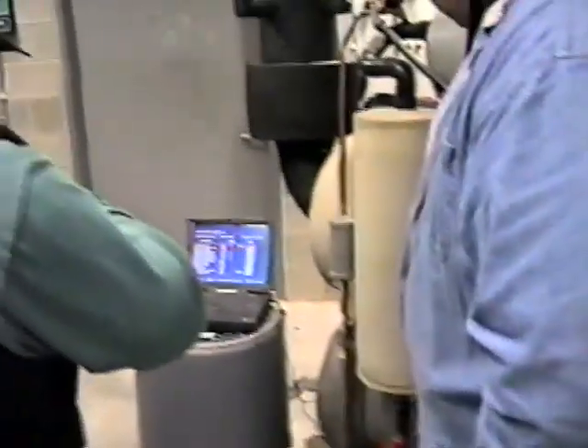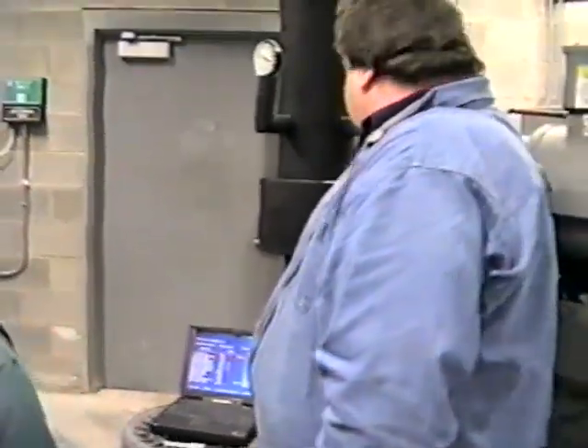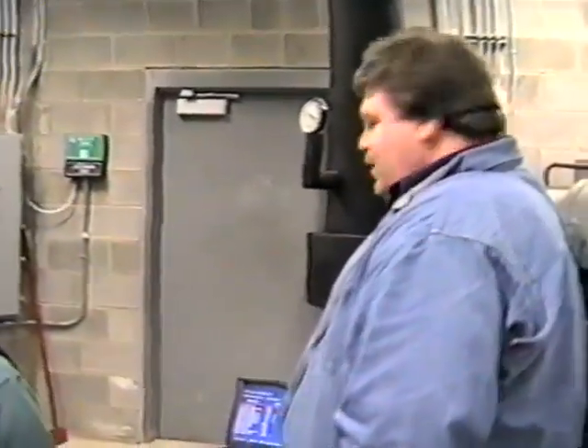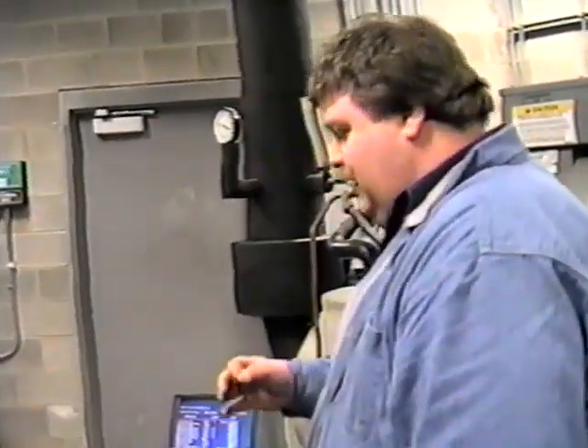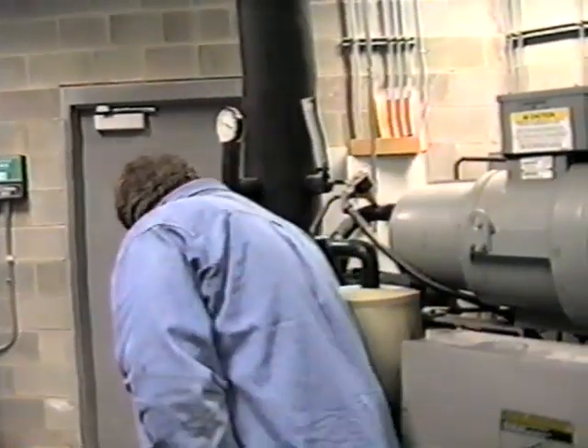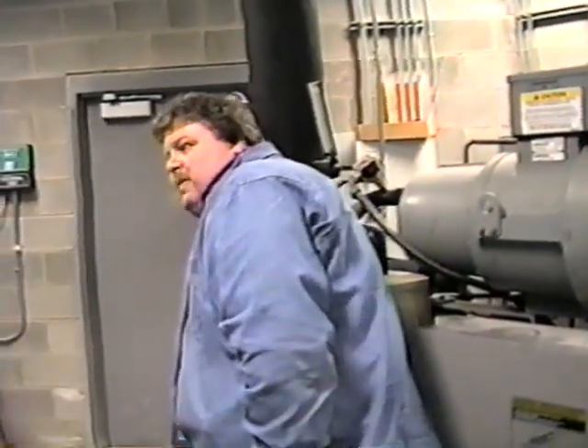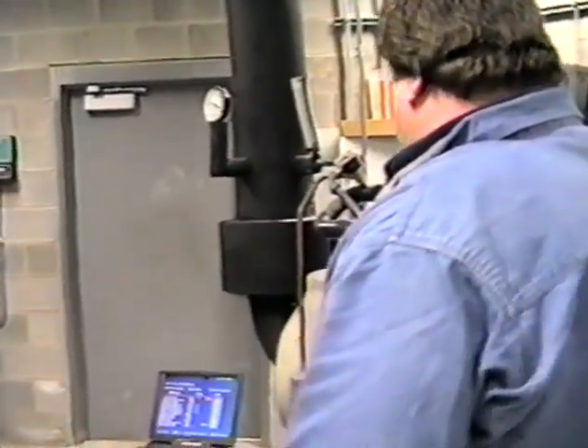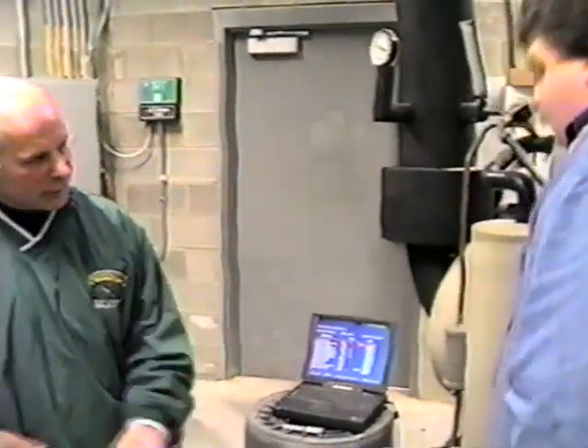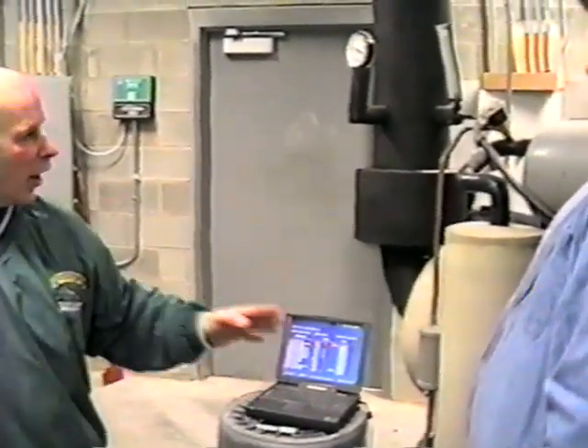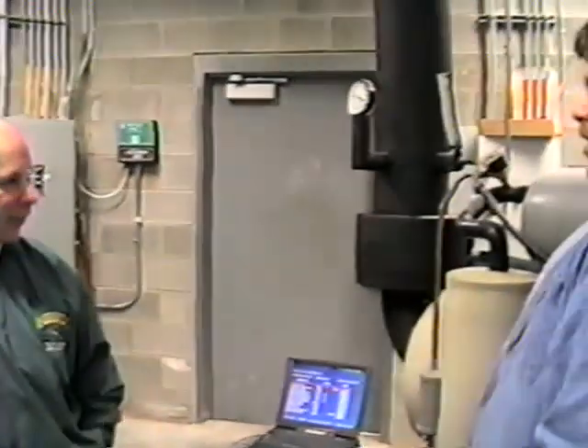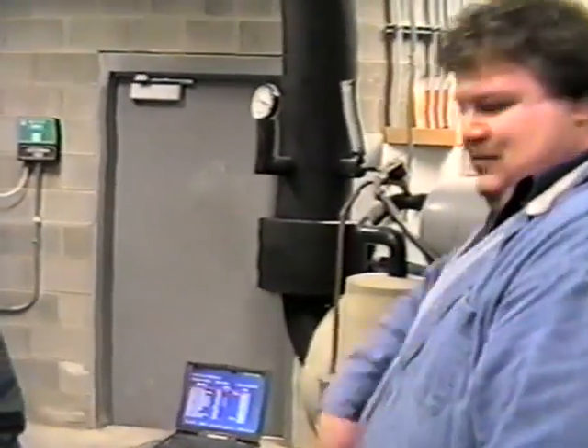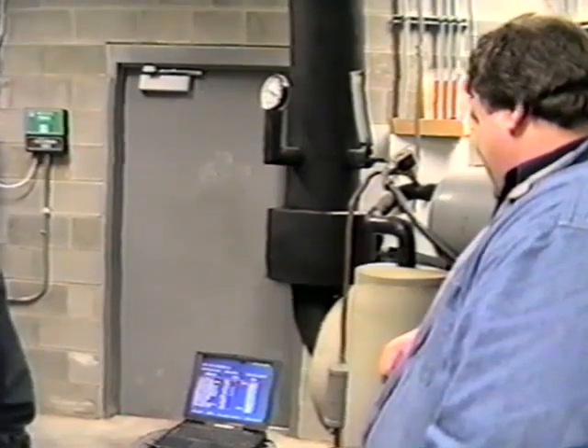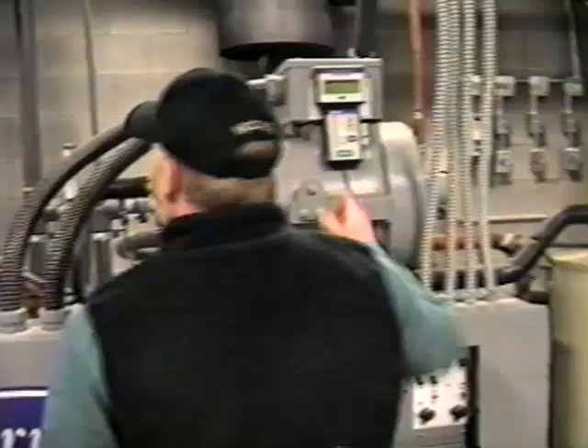Yeah, that's because the chiller barrel underneath, there's moisture underneath the insulation in that. Because we've had it off, anything that had a little bit of frost on it, this was a big ball of ice before behind the sensor. Well, that's all melted. And normally we won't see that much water on the floor. But if there is a drip or two, water is not a concern. Right. Water we don't have a problem with unless it's all over. There you go.